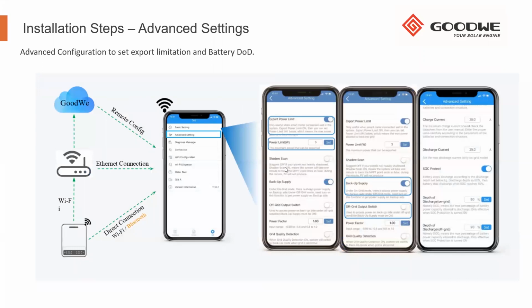Under advanced settings, we've got the export power limit. In most instances, this will need to be enabled. We can set the maximum amount of power going out to the grid. If we can't export, this will be set to 0. If we are limited to a certain amount, for instance, in Cape Town, if we have a 60 amp breaker and we are only limited to 3.5 kilowatts, we can set this to 3.5 kilowatts to ensure that we do not export more than that to the grid.